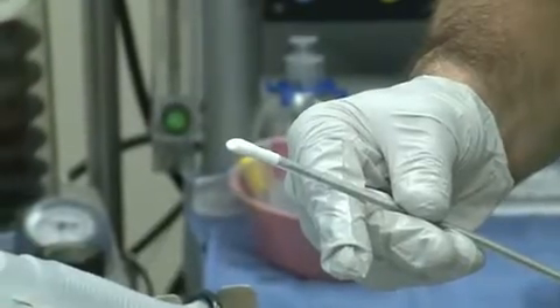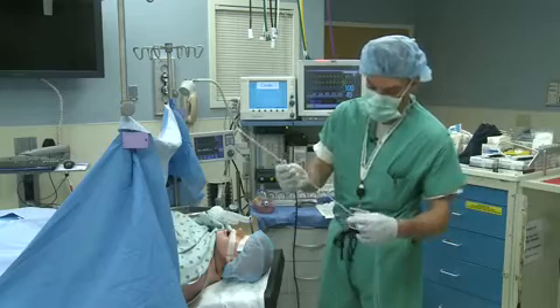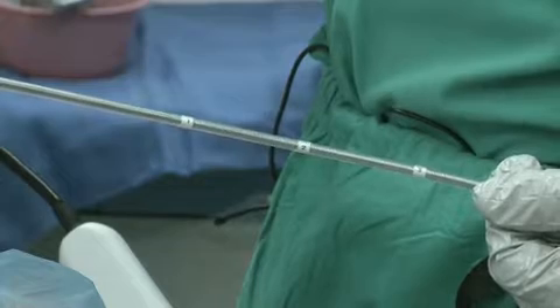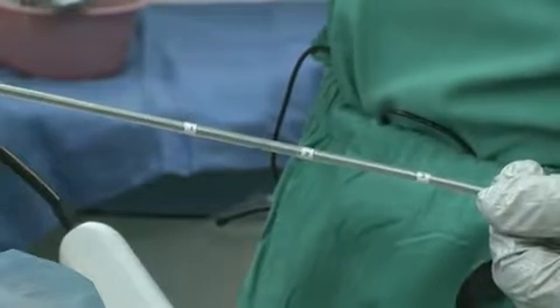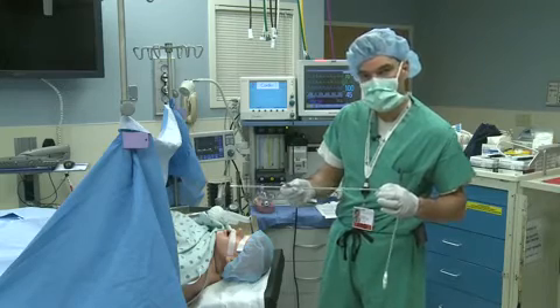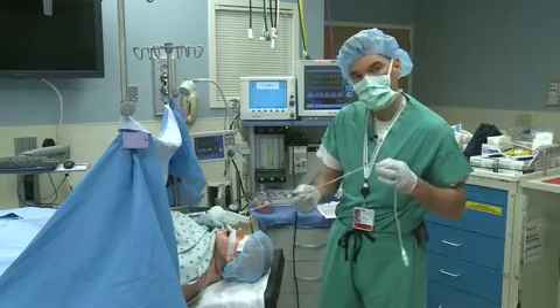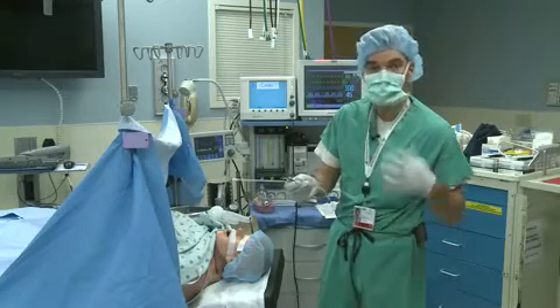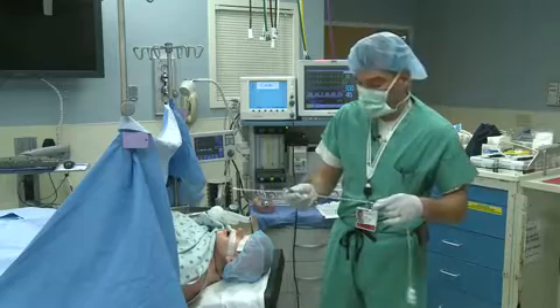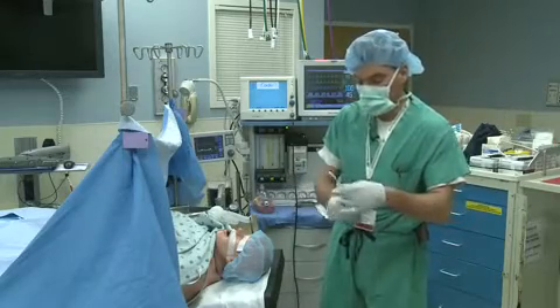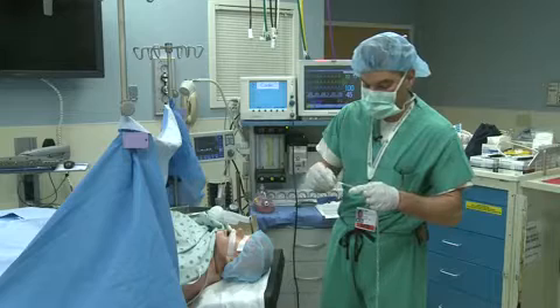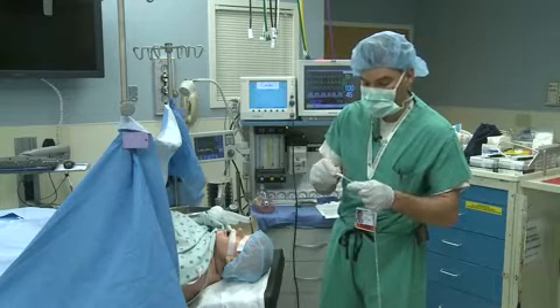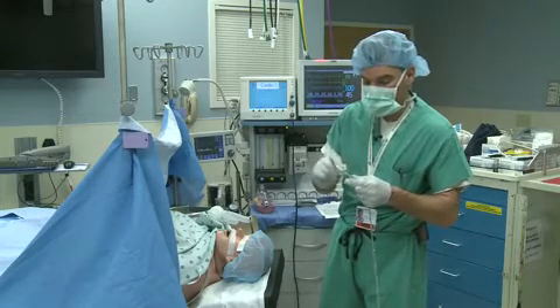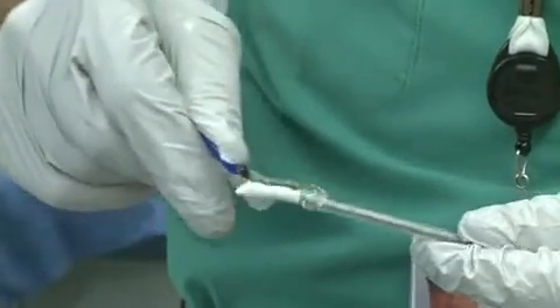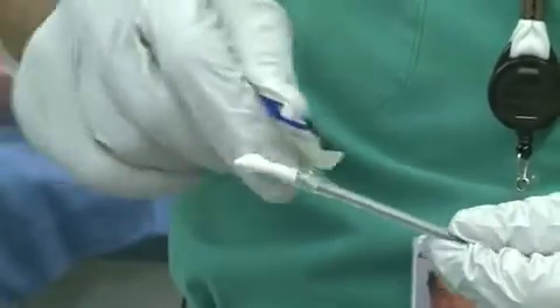There's a bevel to the probe. There's some numbers on the probe, 1, 2, and 3, and they help guide the depth of insertion depending on whether you're going through the mouth, oral insertion, or through a nostril for nasal insertion. And I'll go over that in detail. You need to put some lubrication on the probe. That helps for both insertion and to make contact for a better ultrasound signal when you're trying to optimize and get the signal on the probe.